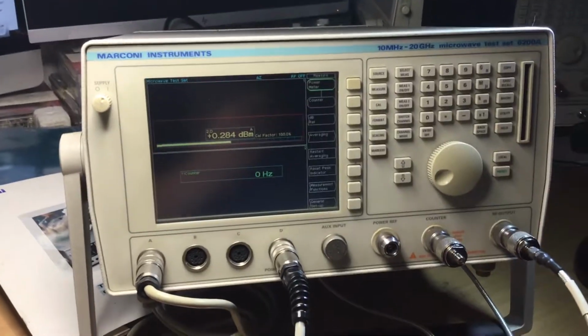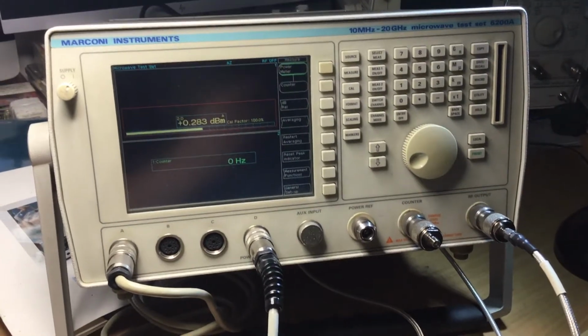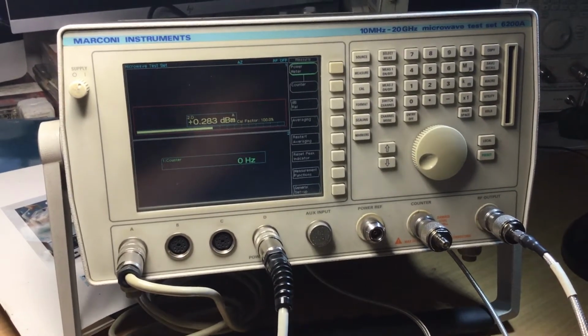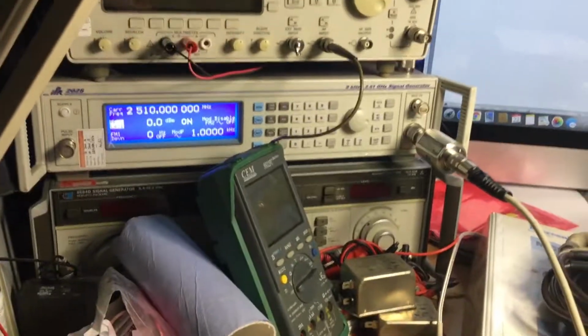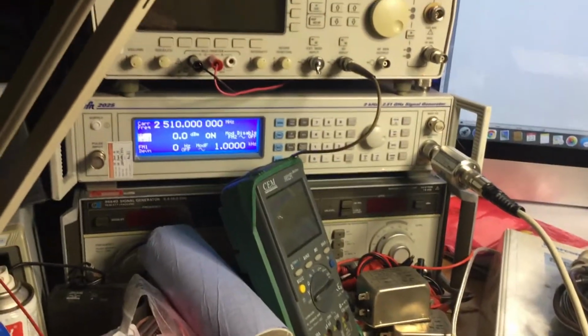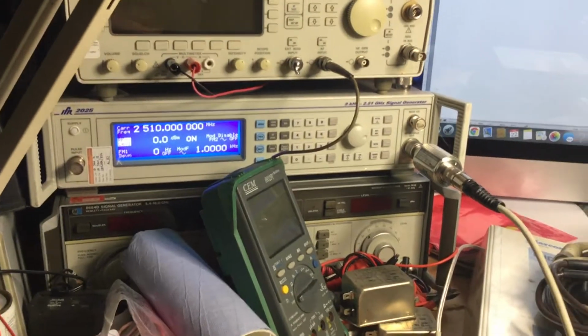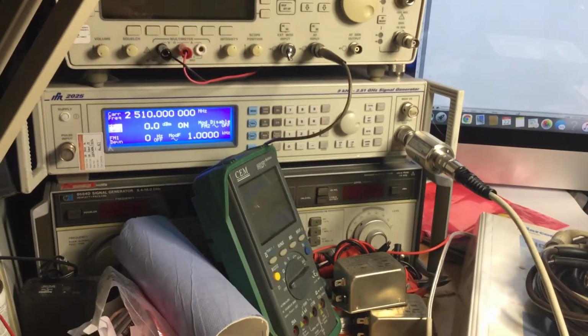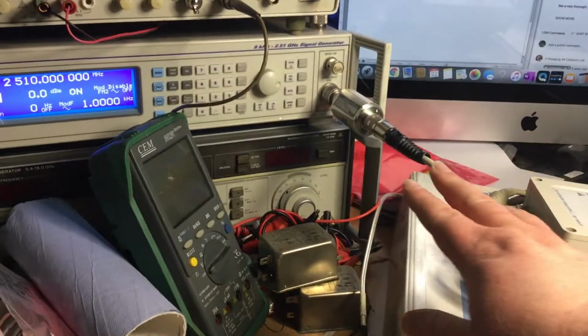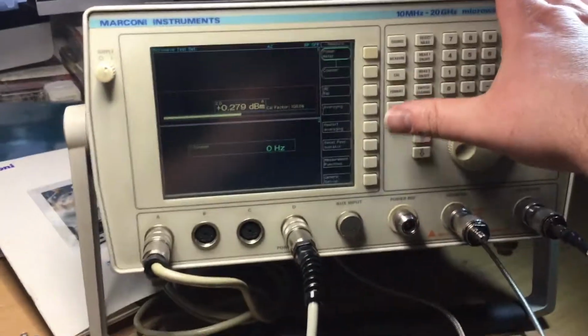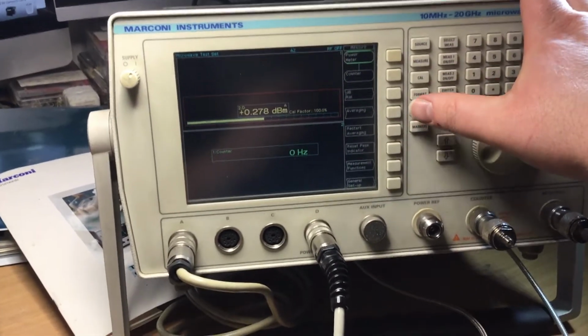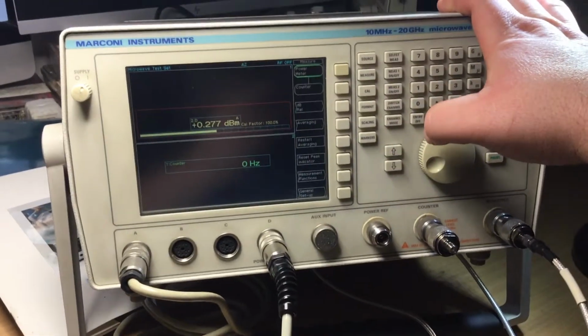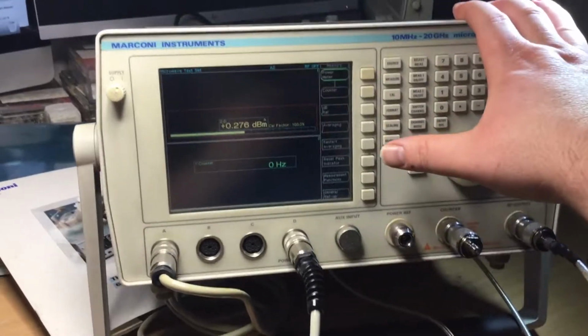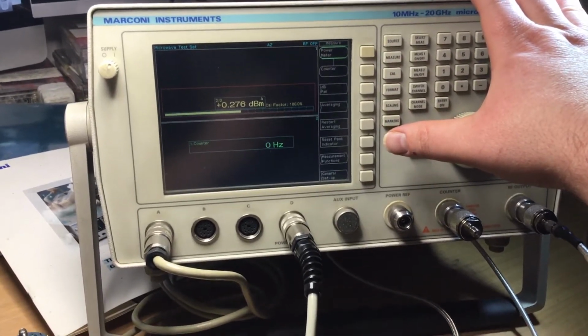So again, this type of instrument, being the extremely accurate instrument, would be used to calibrate this, for example. So we could then go into calibration mode on that SIGGEN and set the output levels across its frequency range using this detector, which we've calibrated on the instrument's calibration port. So these are extremely accurate calibration references, really, which we can use the test set for doing that, because it's designed for that purpose as well.